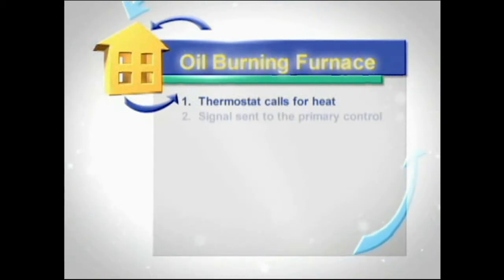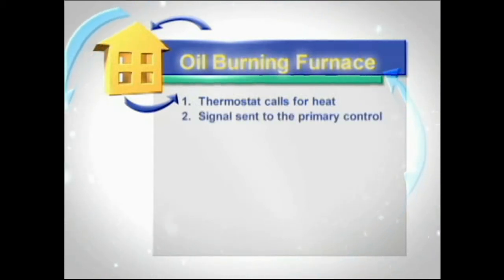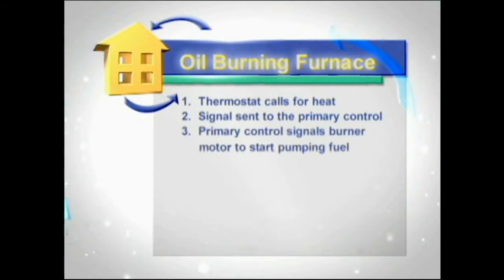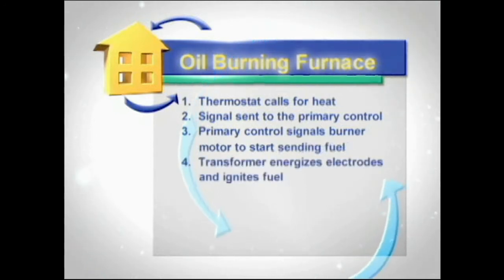It sends a signal down to the primary control. The primary control then tells the burner motor to come up. When it comes up, it also starts to pump fuel. It pumps fuel down through the burner assembly and out through the nozzle. It tells the transformer at the same time to energize. When it energizes, it sends 10,000 volts down through the electrodes, and it jumps between a gap, and that keeps a constant spark, okay, to keep the fuel burning.